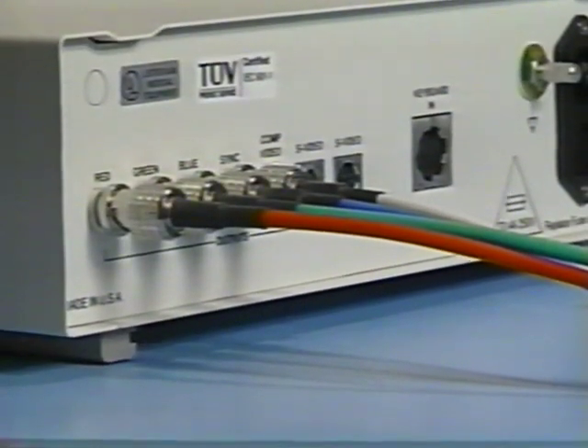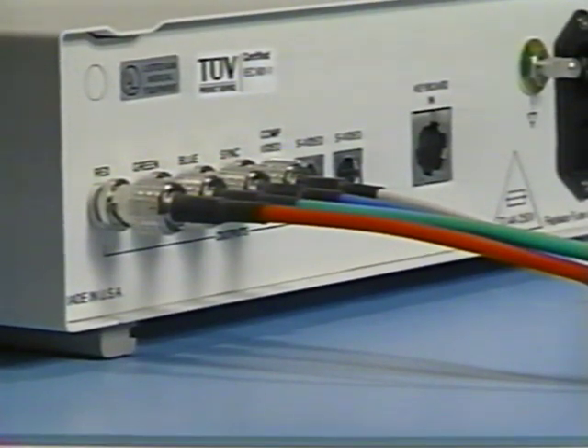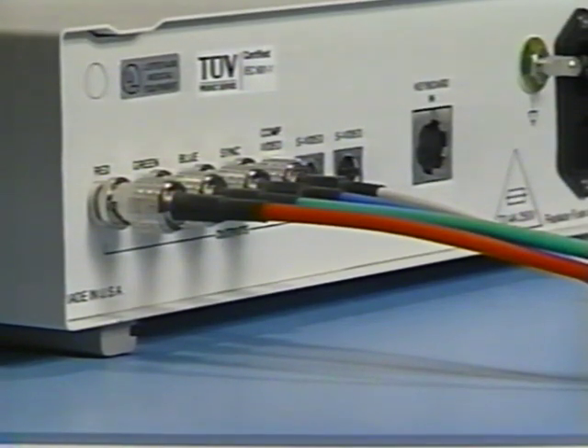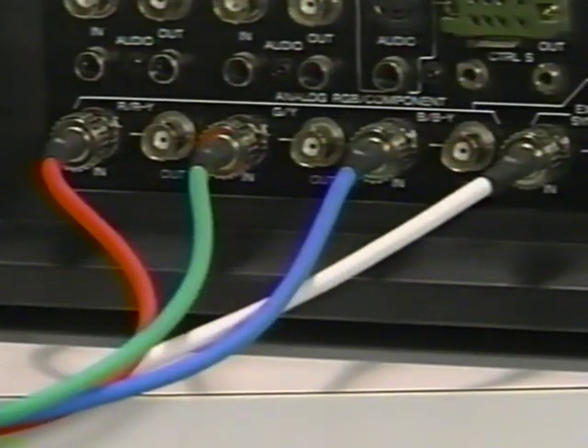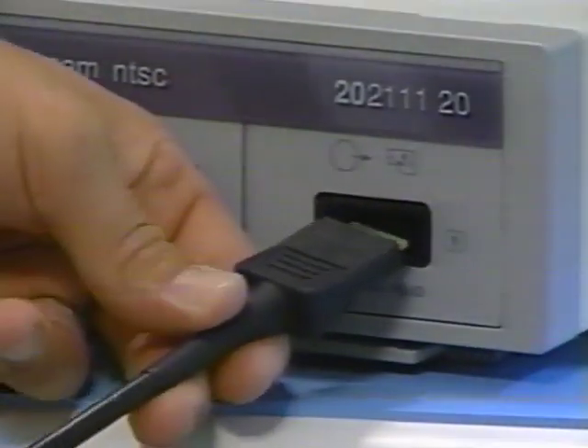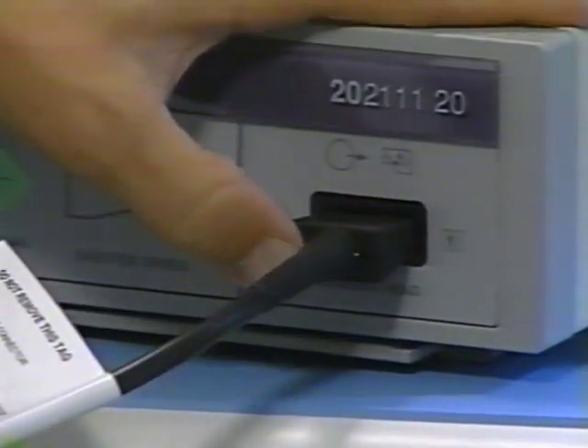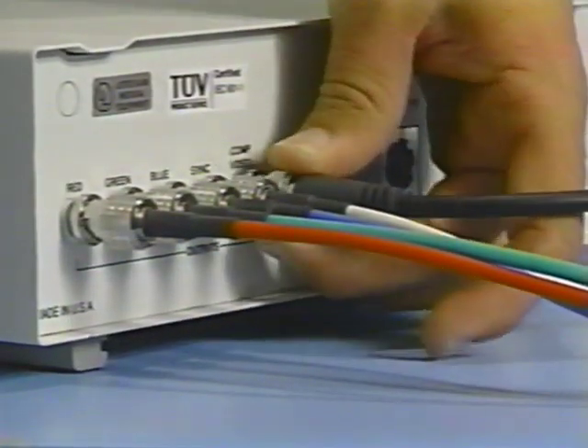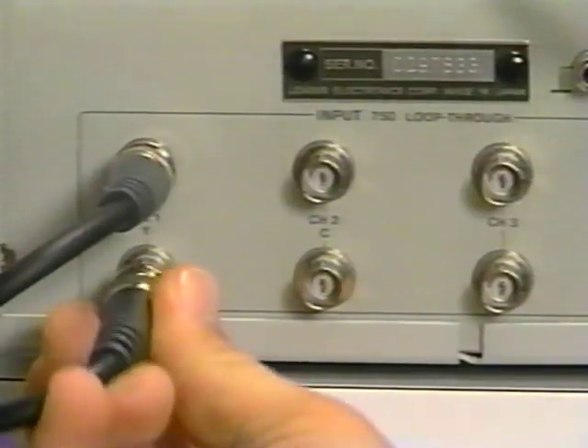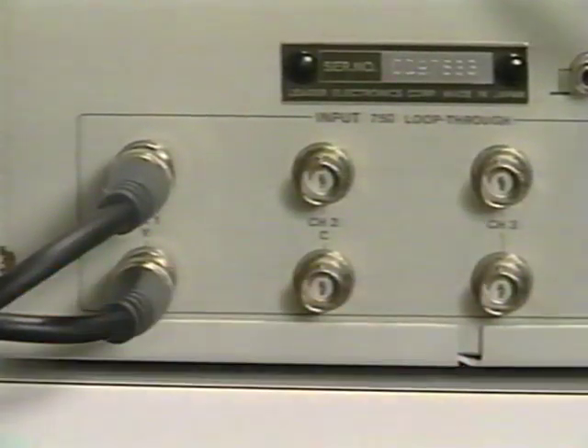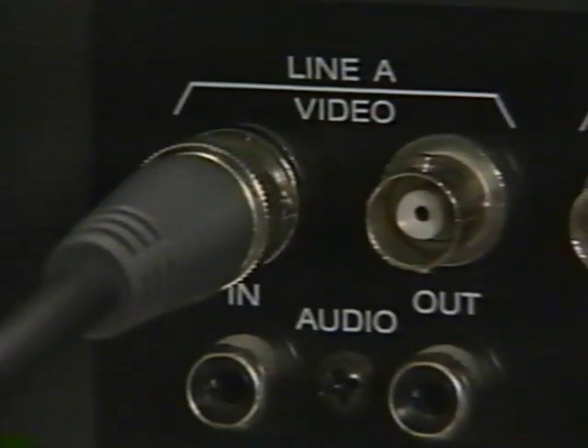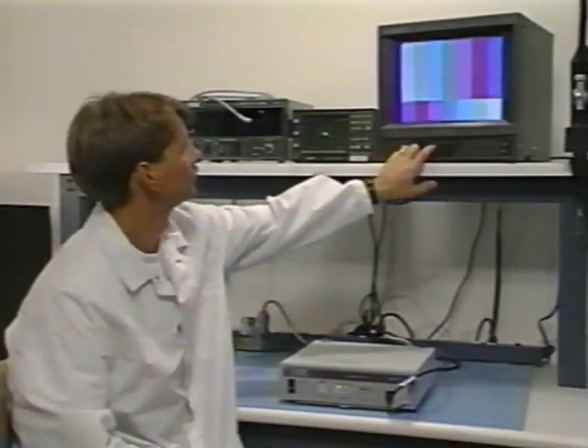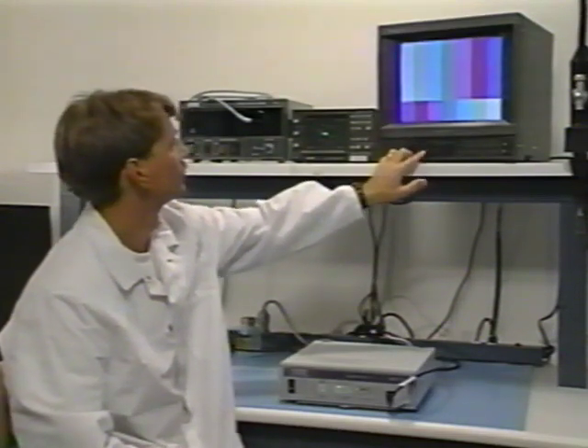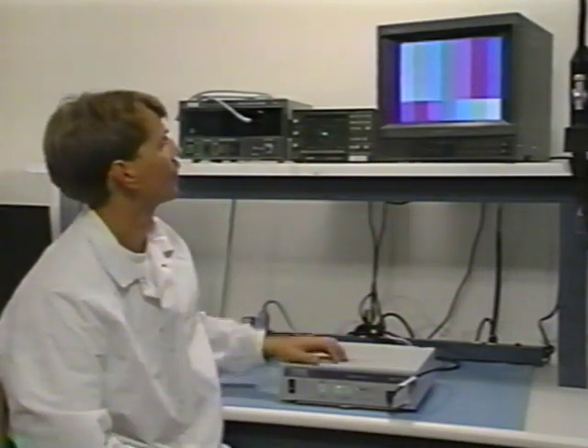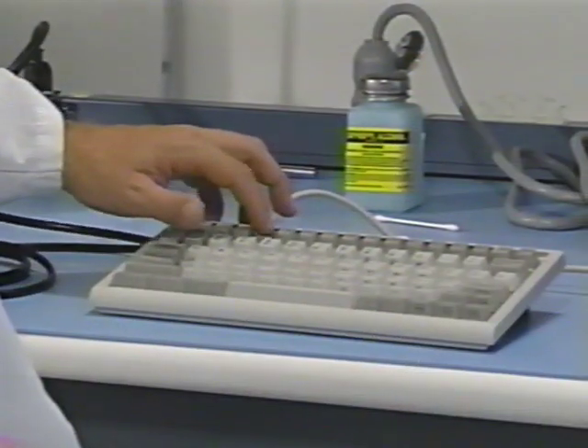First, hook up the video camera by running a YC or RGB cable, if available, from the video output on the back of the CCU to the video input on the back of the monitor. Plug the camera head into the receptacle on the front of the CCU. Attach the CCU video out to the vector scope input using a composite cable. Then, connect the vector scope output to the monitor. Use the color bars function on the camera control unit to properly adjust the monitor prior to testing any equipment.